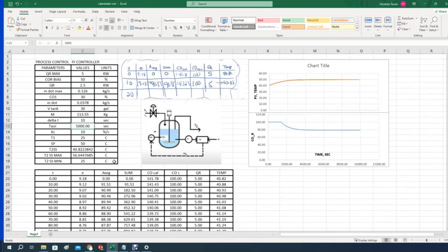Let's drop it to 1,000. Changing the tau I, wait, now I got an overshoot, and you don't want that, because that overshooting will cause it to drop down and then go up, and definitely I don't want that. So, for example, if I keep dropping this from 1,000, you saw what I did with the 500, a little bit more oscillation. How about if I keep dropping tau I, the time constant for the integral part, from 500 to, let's say, 100.